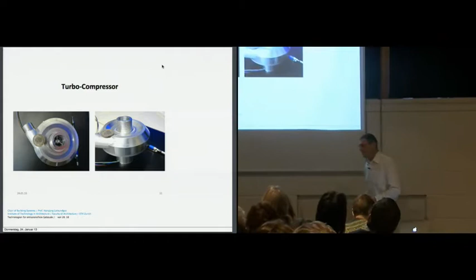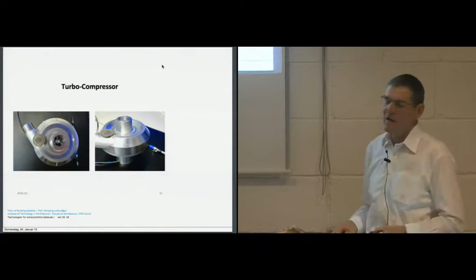So knowing this, that we want to operate the compressor at a low temperature lift, we go into mechanical engineering, and we know that a piston compressor or a scroll compressor is a bad compressor for low temperature lifts, for low pressure differences. A good compressor for low pressure drops is a turbo machine. Now, in the market, there exist big turbo machines, 200 kilowatt to 1 megawatt. They run perfectly. They do COPs of 10 to 12 in the market right now. We have established at the ETH a site with about 300 boreholes at the moment, running with a turbo machine with 1 megawatt, and it is producing the heat we need with a COP of 11. That is in operation right now.